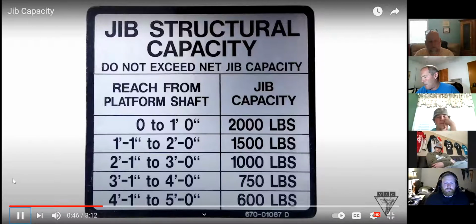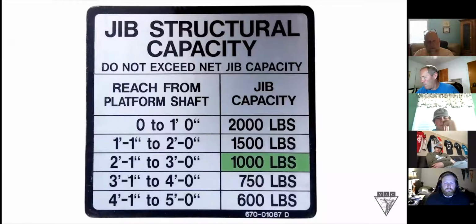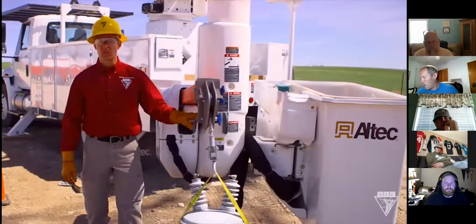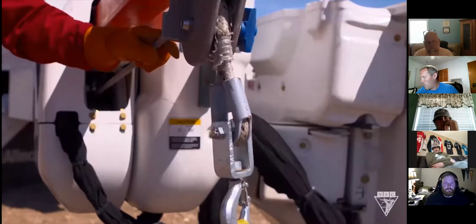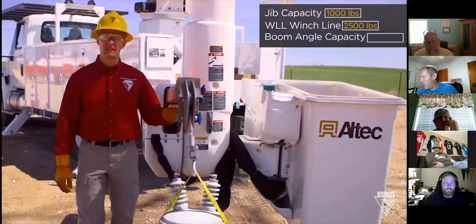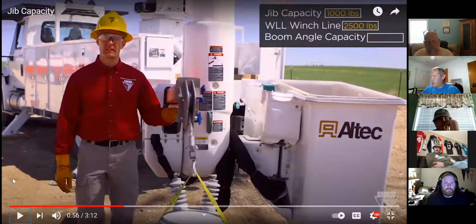For this transformer, I know I'll need to extend it about 2.5 feet, which puts me at a limit of 1,000 pounds. This winch line has a working load limit of 2,500 pounds, so I know I'm safe here. All right, so he's saying he's going to extend the orange part of that jib right there 2.5 feet.